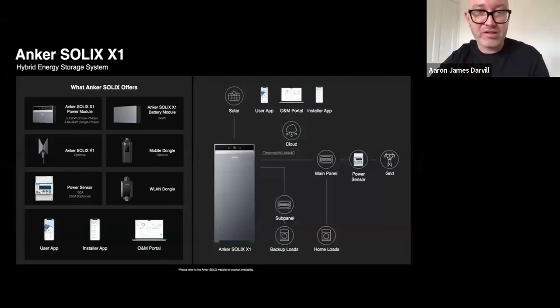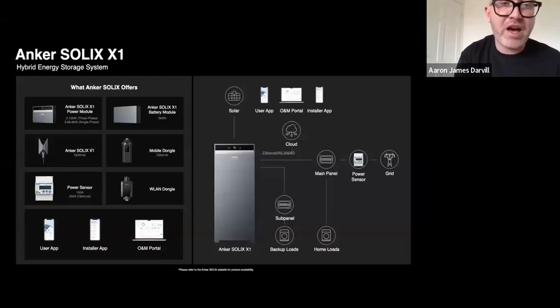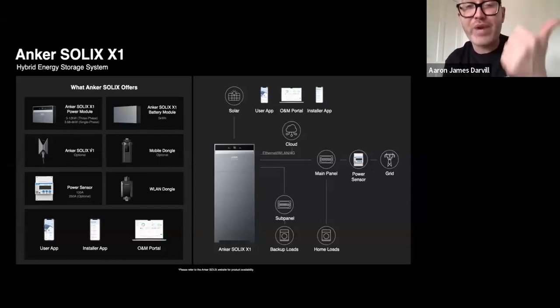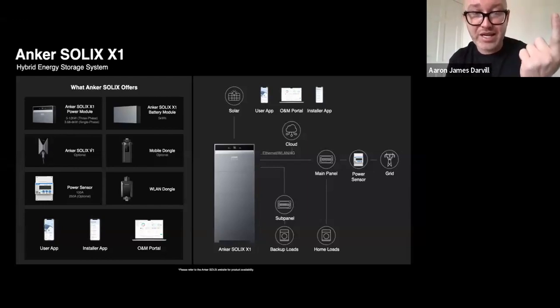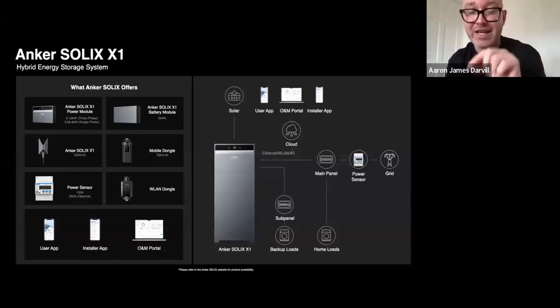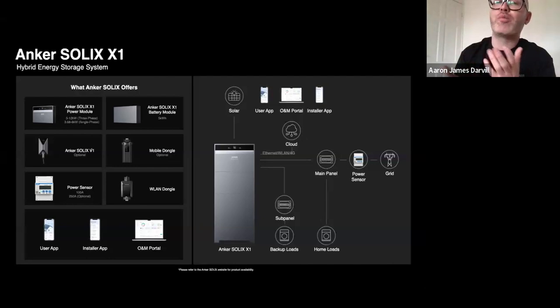So what comes in the box? Everything comes in this box as standard. Anker SOLIX offers the power modules, 5 to 12 kilowatt 3-phase or 3.68 to 6 kilowatt single phase, the battery modules, and then it comes with the mobile dongle. It comes with the WLAN dongle, and the mobile dongle is standard. It can also be hardwired. We have your power sensor, which comes as standard in the box. When we designed the power sensor, we designed it to be a hardline wire. However, we have also created a power sensor with CT clamp, and Segen, as our distributor, have had that sent to them. So you have the option of both depending on your project needs.